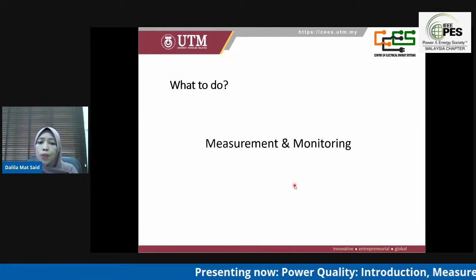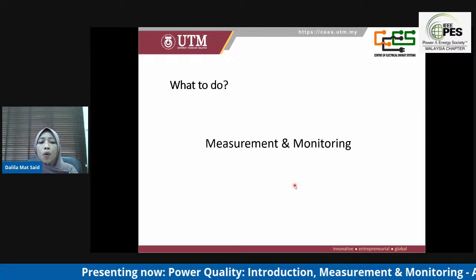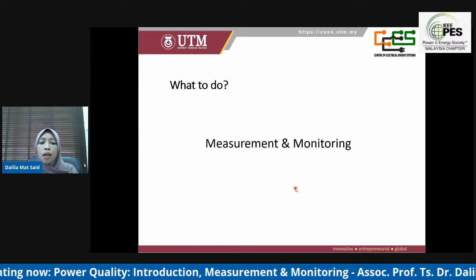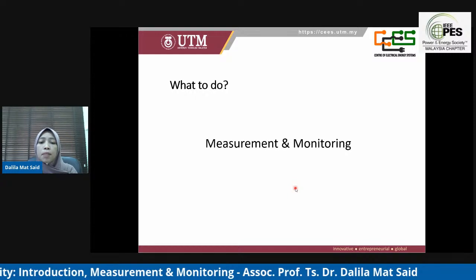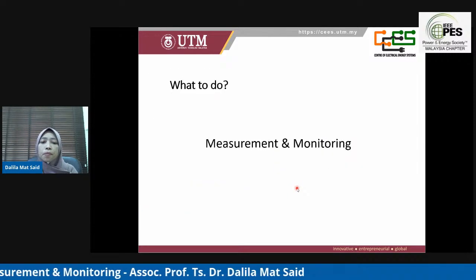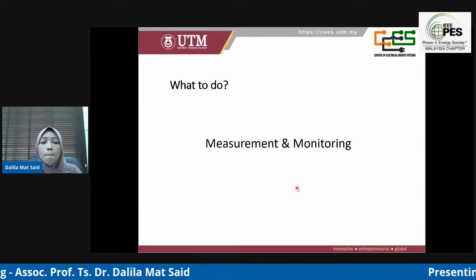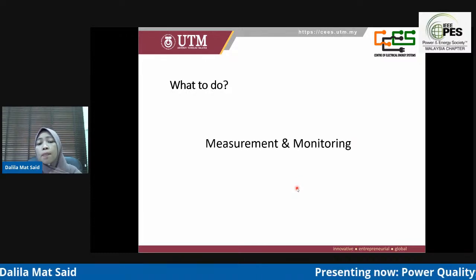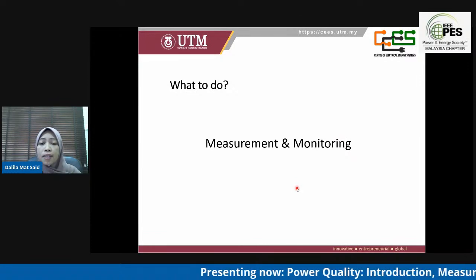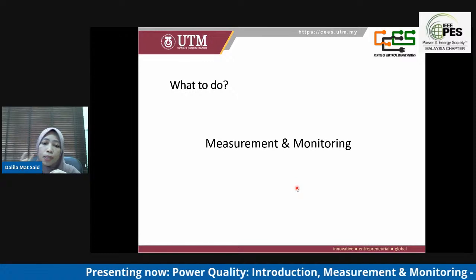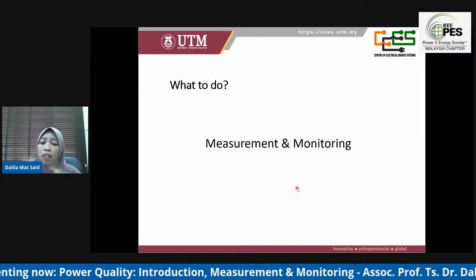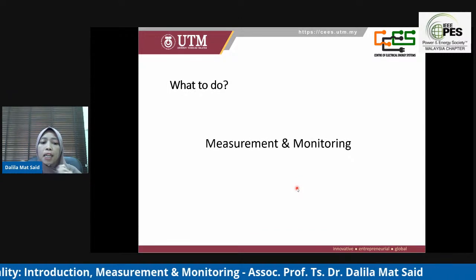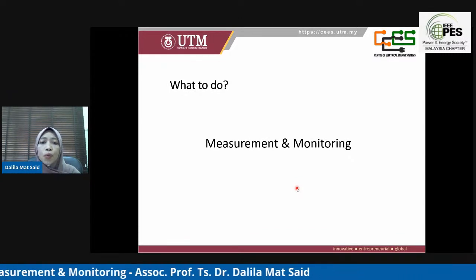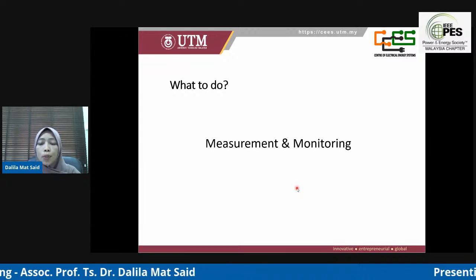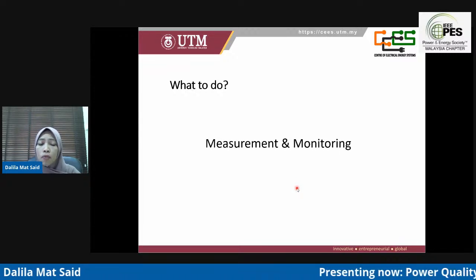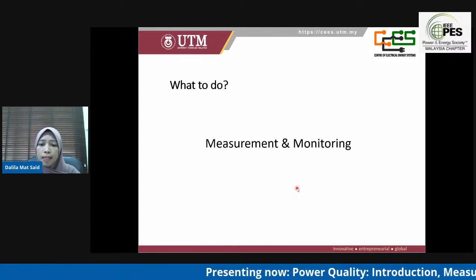So, what do we need to do? Based on the problems highlighted before, PQ measurement and monitoring must be done to solve the power quality problem. Monitoring may be as simple as a person indicating a power quality symptom. For example, we can see the light flickering. So we can say that maybe there is a voltage fluctuation because of the light flickering. But it's best if we do it with a modern power quality meter, which complies with the IEC 61000-4-30 Class A measurement standard.